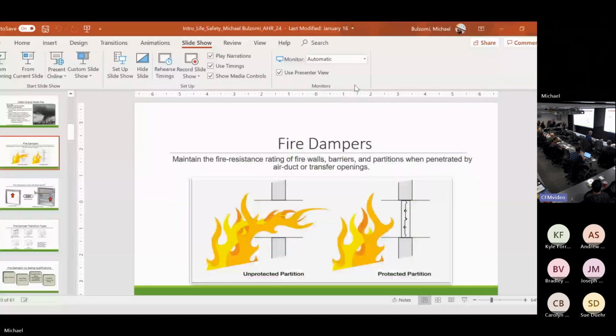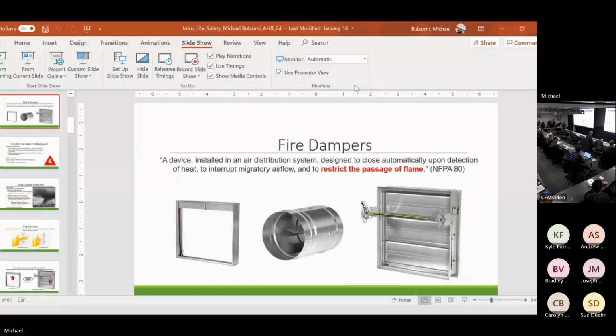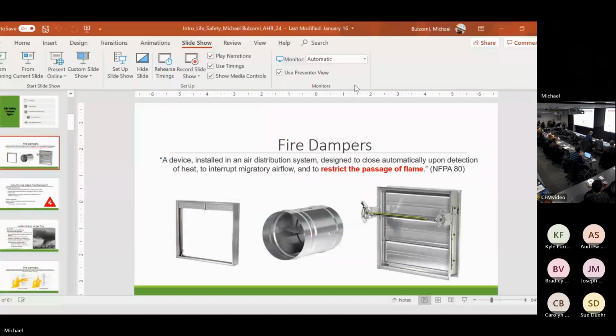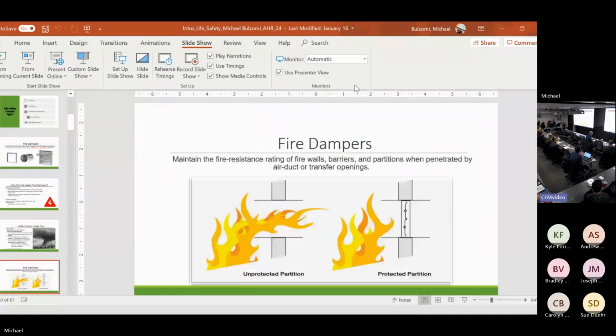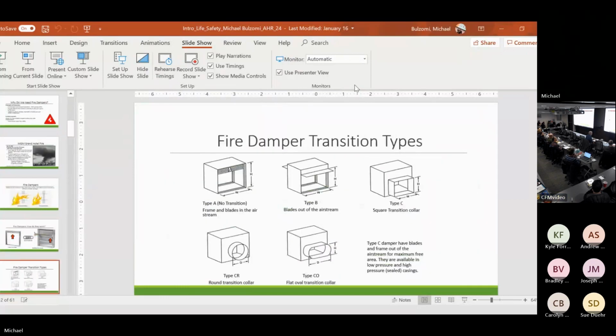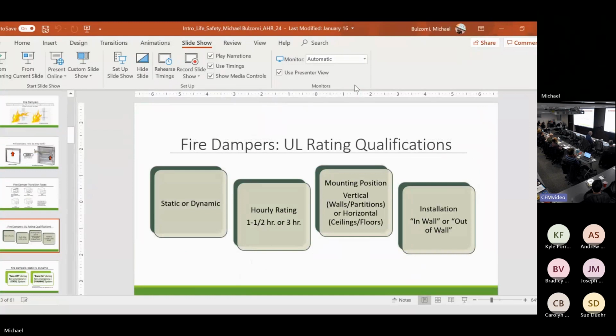I've got a true round damper. I'm going to give you a slide in a little bit to show you the difference between a true round fire and fire smoke damper versus a square damper with a round transition. A lot of trade-offs in pressure drop and installation. So let's talk about some fire damper UL rating qualifications. Fire dampers undergo the test procedures found in UL 555. It's how its tiger earns its stripes.